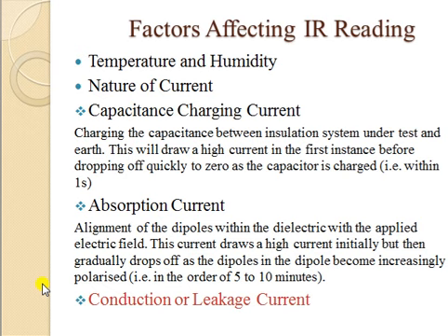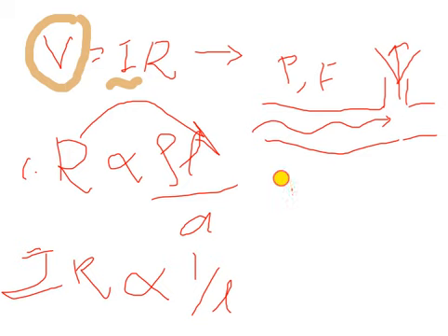Let us focus on the nature of current flowing through the insulation. There are three different types of currents which may be present whenever actual current flows in the circuit. First is capacitance charging current — take an example of a cable, which has a conductor and insulation above it, and there is cable capacitance. This capacitance charging current is used for charging the capacitance between the insulation system under test and earth. It draws a high current initially before dropping off quickly to zero as the capacitor is charged.